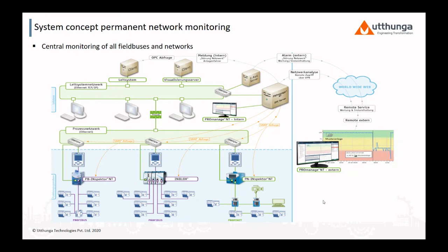And one more thing, you can integrate it with the SCADA, the existing systems. Now you have HMI, and taking a laptop is very difficult in the premises. Then you can integrate it with your HMI, the available monitoring systems in the production line, or you can integrate it with the SCADA over RJ45. There are standard reporting options like the potential-free switching contact, and you can do an SNMP trap. For example, if you're using ProManage, you can use the SNMP trap. Like that, you can integrate it with your existing system.